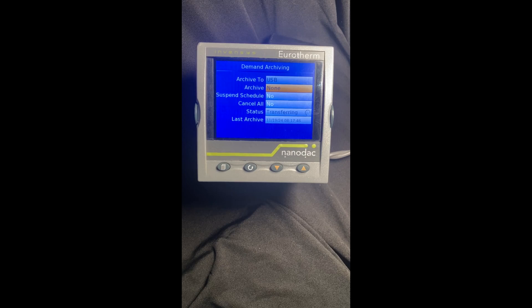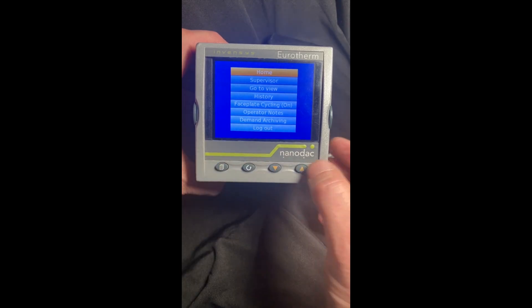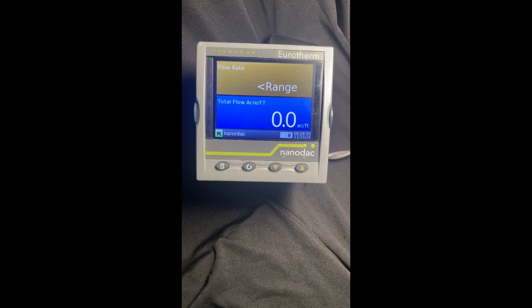The last thing to consider — depending on your company's security requirements — is that in the supervisor level there is a little more access to parameters, so you may want to log back to level one when done. We are complete, so let's hit our page key, go back to log out, and now we're back to level one. As you can see the demand archive doesn't show up and the controller is back to normal run mode. Hope you find this helpful — drop us an email or give us a call if we can answer any questions. Thank you.